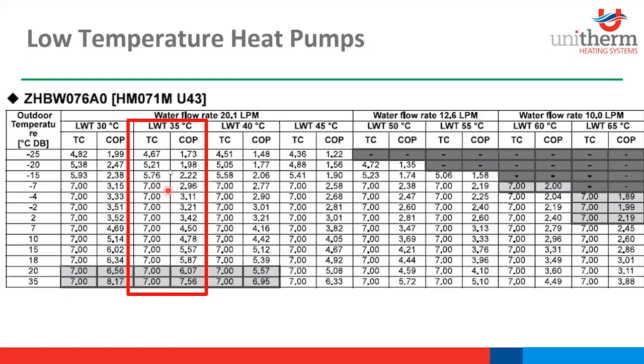So with 7 degrees down to -7. Our heating test standard is EN 14825, and that's taken with air at 7 and water at 35. So with air at 7, water at 35, we have a COP of 4.5. There's a low degradation of the COP, so we're still getting a COP of 3 even at -7. And we'll be running these on a lower weather compensation curve between 30 and 35 degrees. So even at -7, you have full capacity, and between 3.15 and 2.96 is your COP.